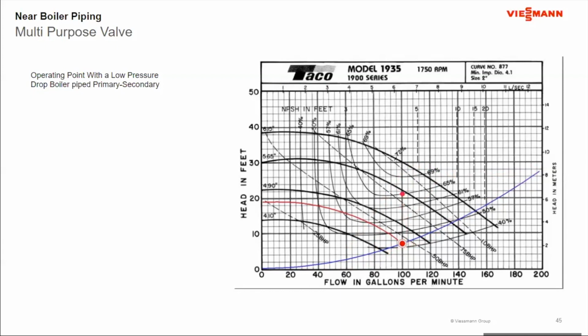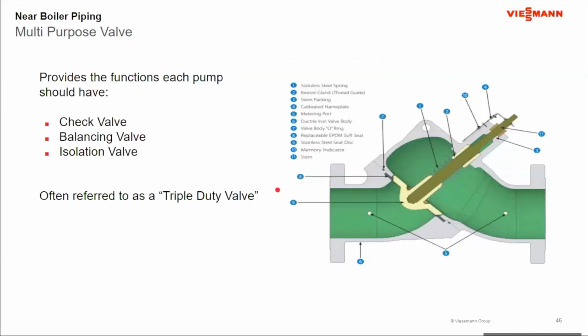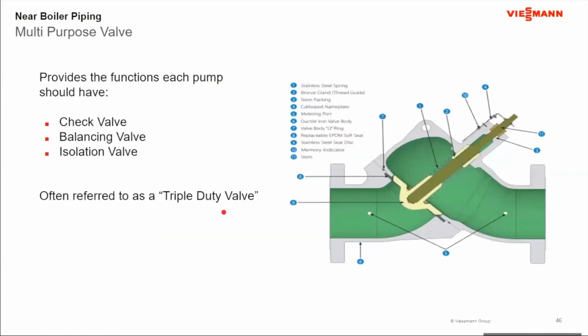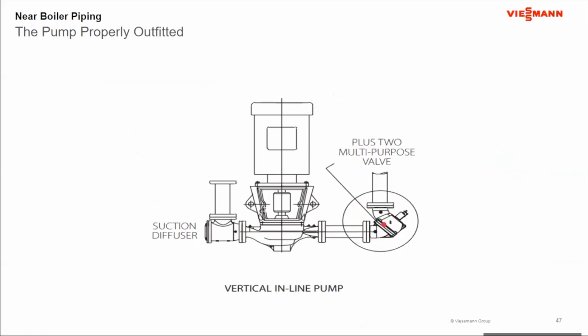So from an aspect of application in near boiler piping, the balancing valve should be there, which means from a standpoint of equipment, we might as well do it through a triple duty valve, a multi-purpose valve. That way I pick up the check valve, I pick up the balancing valve, and I pick up the isolation valve in a single package. So when I look at a pump in the system, I should see something like this. Here's my suction diffuser because my mechanical room is tight. Here is my multi-purpose valve because I need the check valve, I need the balancing valve, and I need the isolation valve. So that's what I should see around every pump, unless I have the 10 pipe diameters that come in straight on this side here, okay?